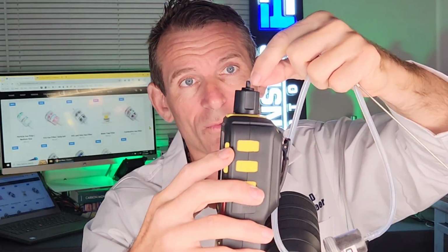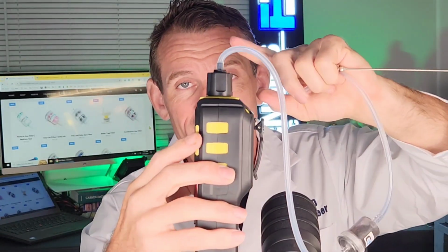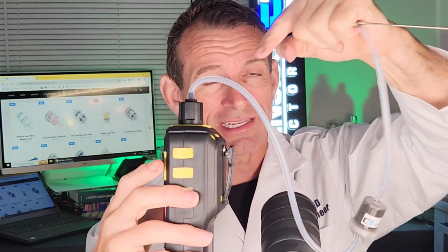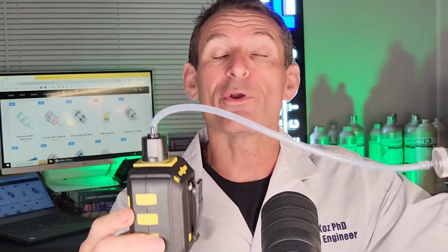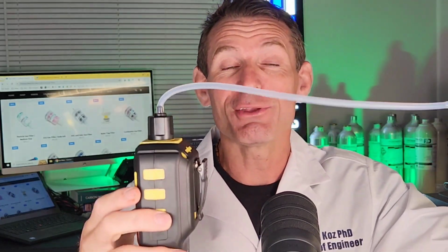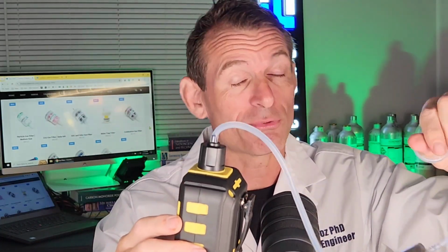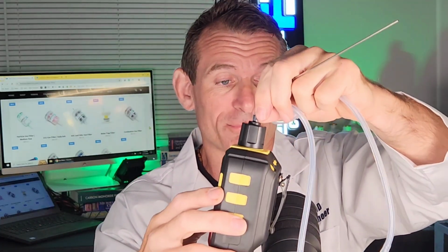That's why we are using a gas analyzer with a built-in pump, because it draws the air, creates a negative pressure. Without a built-in pump, you won't have the air movement, and you wouldn't believe actually how many people miss that point. It's very important. If you're trying to move air with a probe, you need a built-in pump or an external pump to create the negative pressure. And then we have our simple filter in line with our gas analyzer and our probe.